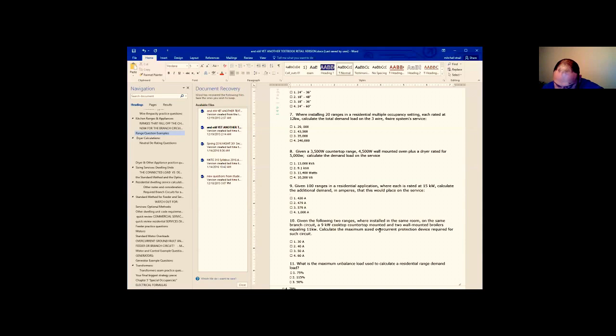I never saw a question like that. But you might have seen a dryer here or there thrown in with an appliance or service calculation, but typically there's not a derating used with dryers. So if you do have a calculation that's got square footage, a dryer and a range and a bunch of other stuff in it, the dryer is usually just going to be 100% of whatever the nameplate is because it's usually not deratable. Unless they give you 4,500 watts, then you have to bump it up to 5,000 minimum.